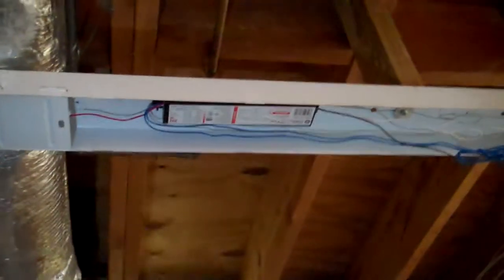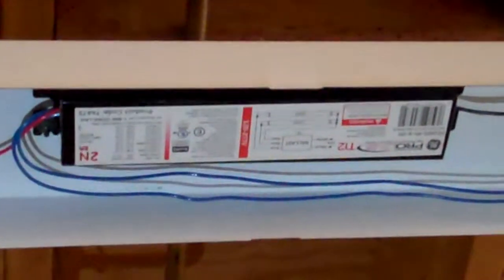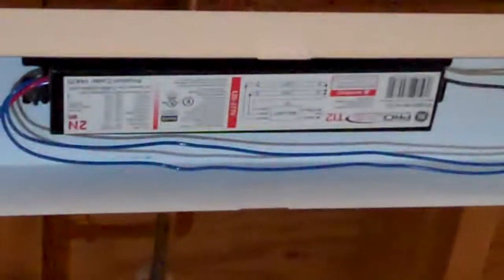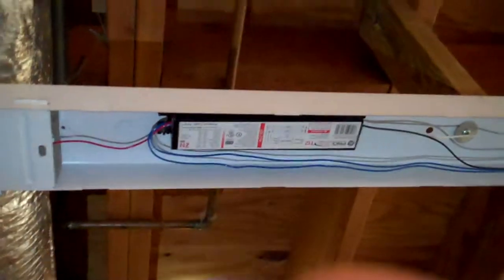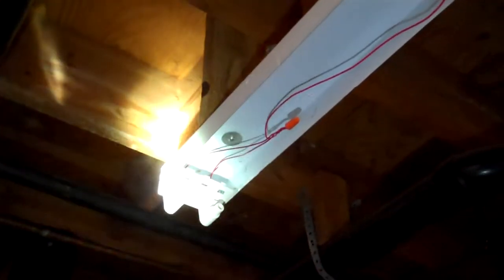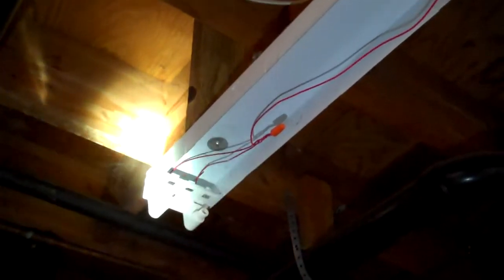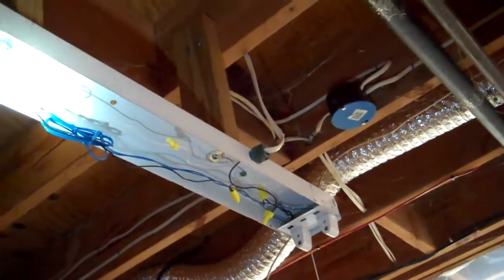I had to put in a new ballast. The old one was what they call a magnetic, like a big transformer. These newer ones are electronic and so I had to basically just take and tear this down and rewire the ends here with new leads coming out of the new ballast here. Basically just stripped the damn thing out and started over.